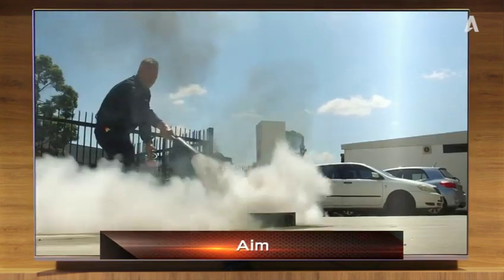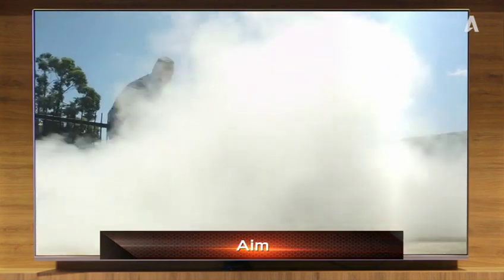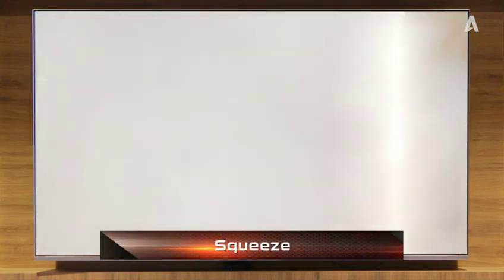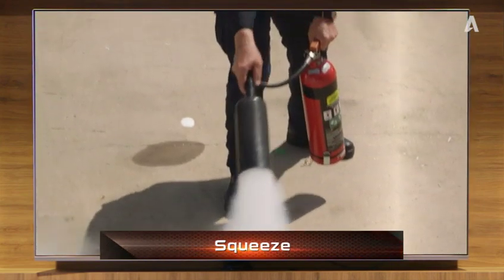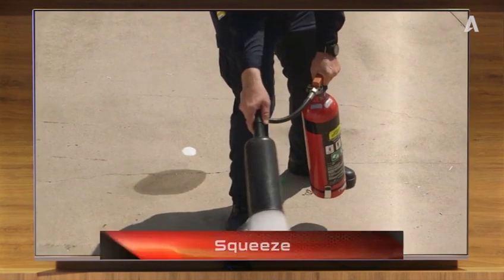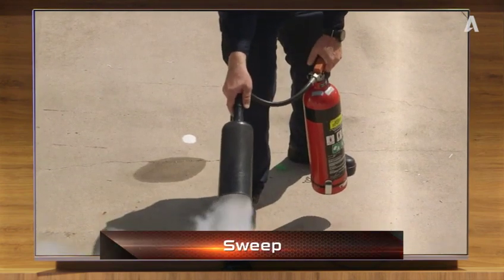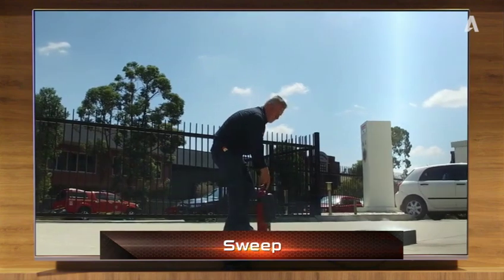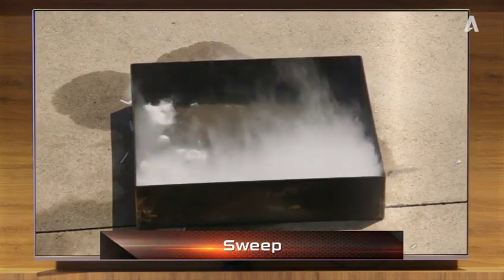A is for aim low at the fuel source at the base of the fire. S is for squeeze the lever above the handle. You release the handle to stop the flow. And the final S is for sweep. Aim low at the base of the fire and sweep until all the flames are out. At this point, you need to watch for reignition, and if this happens, you need to repeat the process.